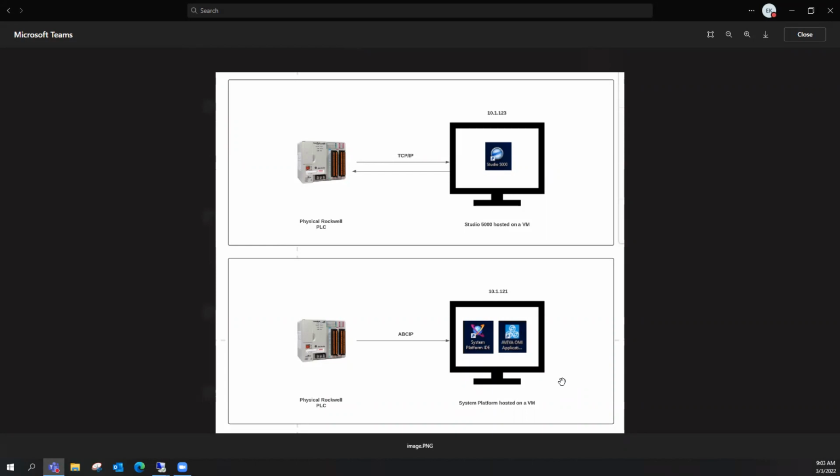And we're using that on a VM to establish the communication link to the PLC from that PLC programming software, to download the simulation code to the PLC and also establish the IO, right? That's done through TCP/IP, as you can see in the middle. It's an ongoing link between them where we're uploading data from the PLC and we're also downloading data to the PLC. So once again, the goal of that VM is to establish the tags that we will be bringing into System Platform later, and then downloading the PLC code that simulates those tags to the PLC. Because we currently don't have any physical IO connected to the PLC, we created a PLC program that simulates those tags directly from the PLC. So that's what that top half of the architecture does.